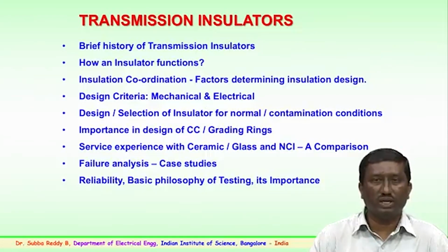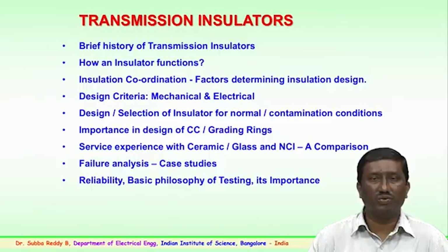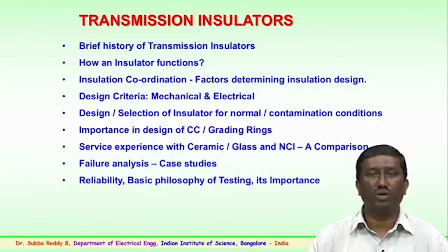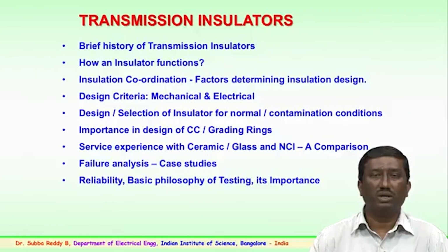The first component is the transmission insulator. We will briefly look into the history of the transmission insulator, how an insulator functions, how insulation coordination works, what factors determine the insulation design for transmission insulators, and how important that is. Then the mechanical and electrical design criteria to be adopted before insulators are used in the transmission system. Then we will look into the design and selection of an insulator, particularly for a normal condition or a contamination condition. This depends on whether the transmission line passes near polluted zones, normal areas, or heavy rain or heavy fog areas. Depending upon the area where the transmission line passes, the selection of insulators is done. We will discuss the selection and design aspects of the insulator for various conditions.